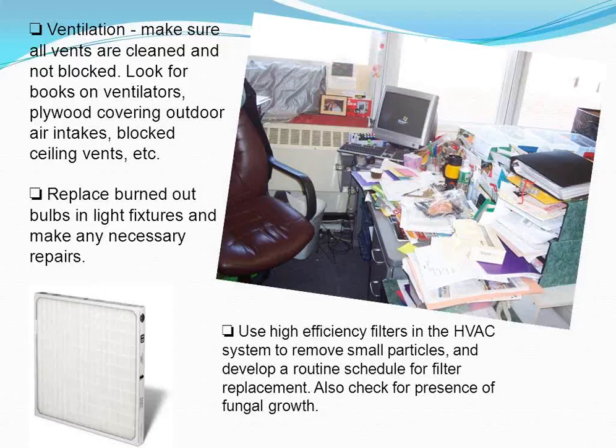We recommend changing filters out every season, four times a year. And of course, the filters are really there to protect the equipment. Everyone thinks, oh, let's put in HEPA filtration, but the ventilation system usually can't handle filters of that grade. That's usually used in vacuuming equipment when you're doing rugs. Right. But you do want fairly high efficiency filters to take out some of the larger particles. Keep the ventilation system clean, and it's going to deliver good air quality. If it gets dirty or wet inside the air handling unit, for example, or the ductwork, you can have a potential mold problem.